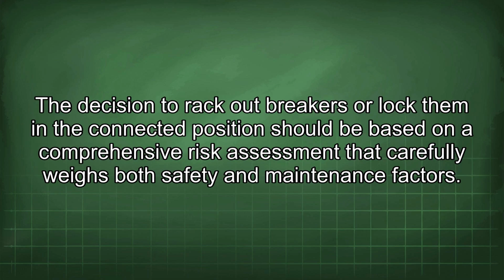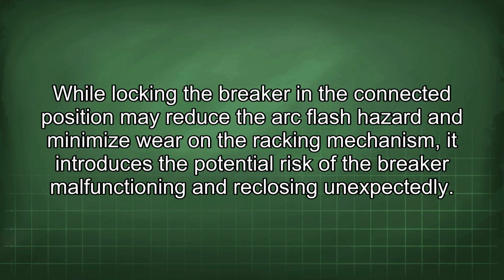The decision to rack out breakers or lock them in the connected position should be based on a comprehensive risk assessment that carefully weighs both safety and maintenance factors. While locking the breaker in the connected position may reduce the arc flash hazard and minimize wear on the racking mechanism, it introduces the potential risk of the breaker malfunctioning and reclosing unexpectedly.